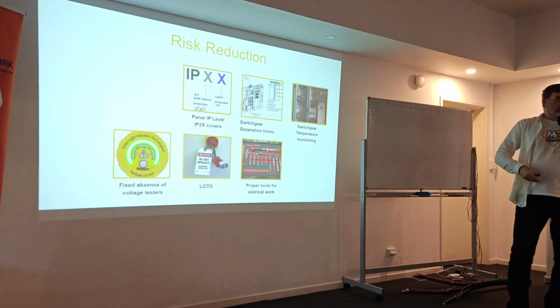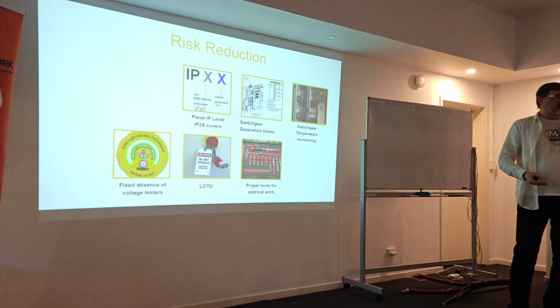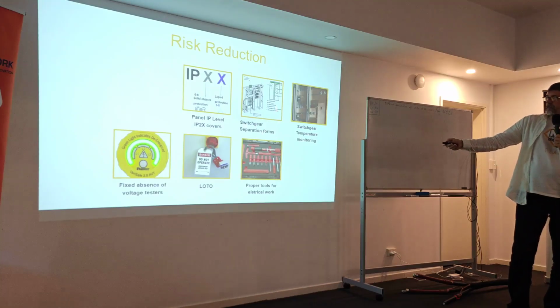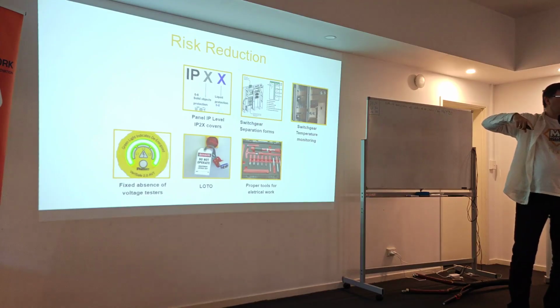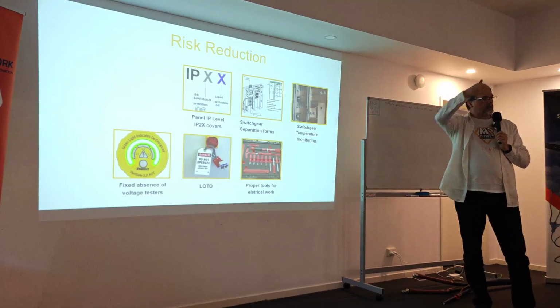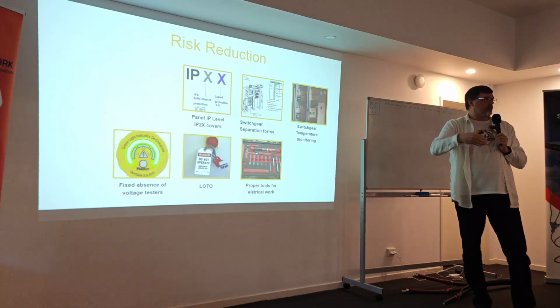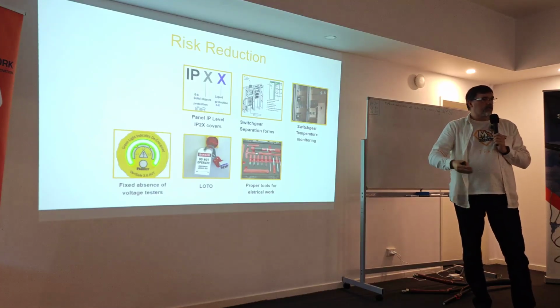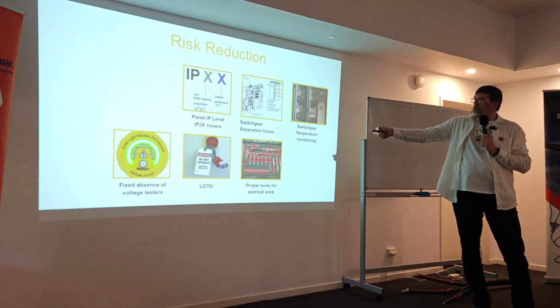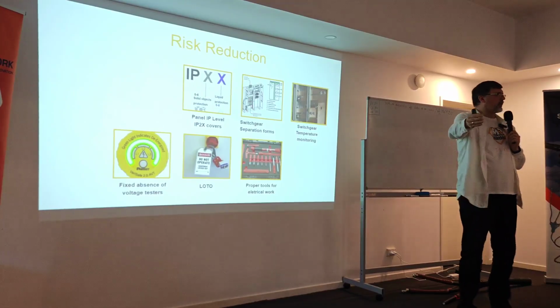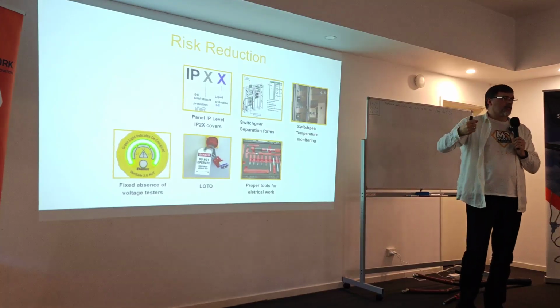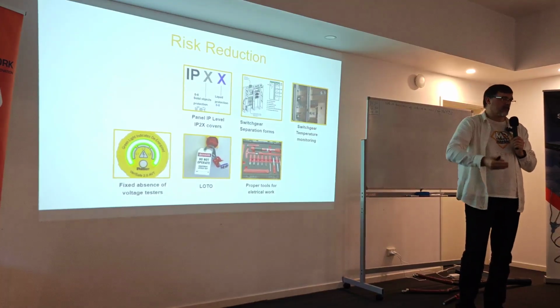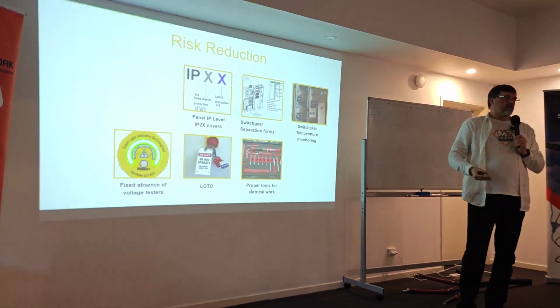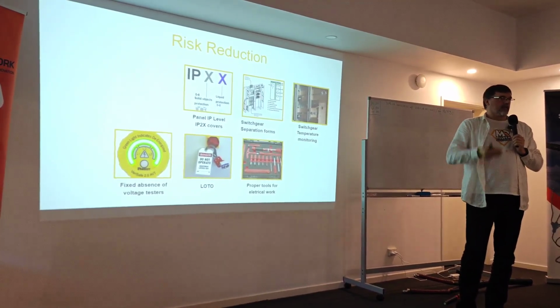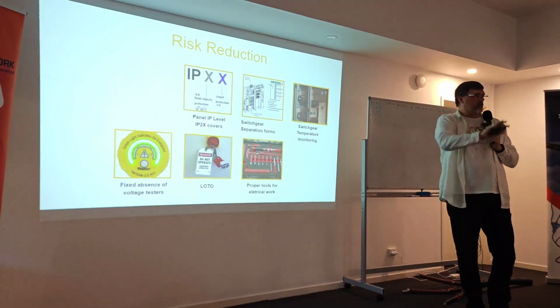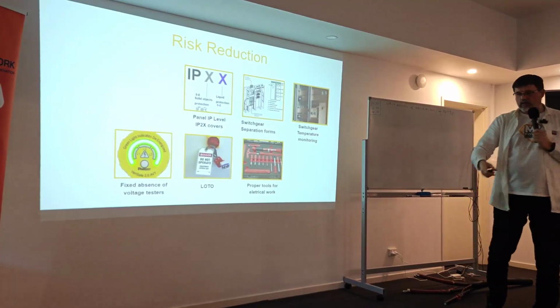Because there is a plexi. Plexi is not the arc-rated topic, yeah? But it's treated as a cover. Separation form, that's what you see on the previous photo, that separation forms are just the way how you design. Physically, you have to design switchgear. You have to order 4B, 3A, 2A separation form, which means that, for example, cable connection is separated from the breaker. So that was this discussion on Monday that we have with 1 door, 3 doors, and so on. Typically, when you see 3 doors breaker, switchgear, it's 3A, 4B separation. That you have everything separated, yeah? So control system, breaker, cable connection, and the buses internally as well.